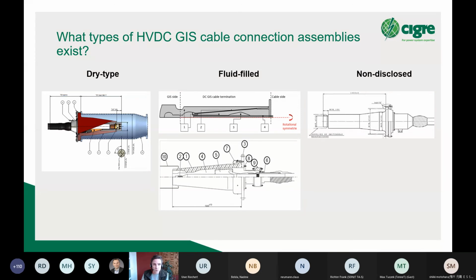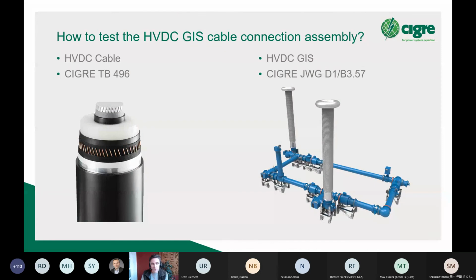There is a problem though with these designs, and that is that we don't really know yet exactly how to test these. So we can have two different types of tests. There are the cable tests, as have been described in the CIGRE technical brochure 496 for HVDC cables with extruded insulation. And then on the other side, there are the tests which were just presented by Professor Neumann from the CIGRE Joint Working Group D1/B3.57. And they are not the same.